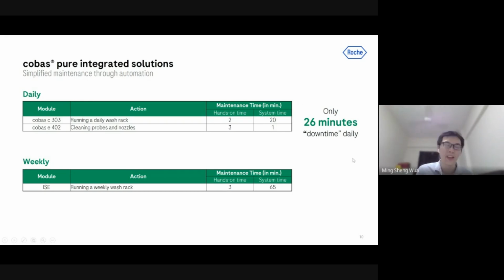The rest of it is done by the system itself. So in a day, if let's say your lab operates 24 hours, the only time that you're not able to use the analyzer to run any test is this 26 minutes, or I can say half an hour of downtime. Other than this half an hour of downtime daily, you'll be able to run your samples anytime you want. In terms of the weekly and also bi-weekly maintenance, the maintenance is cut down by a lot compared to the previous generations of the analyzers.